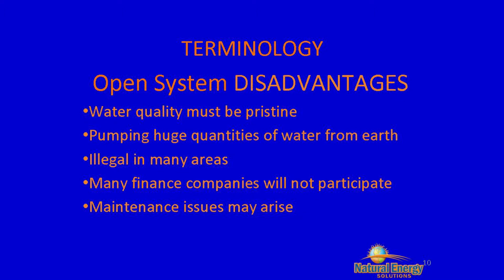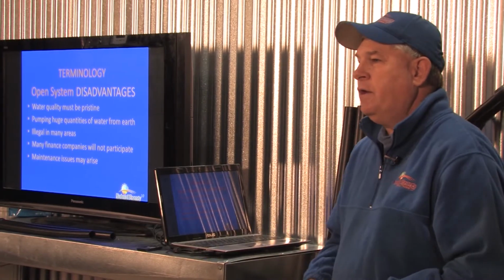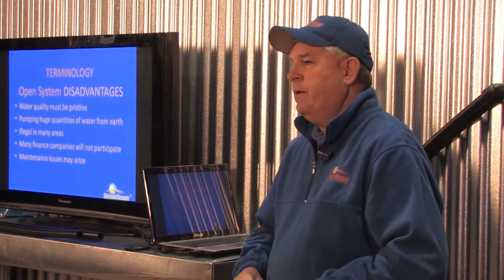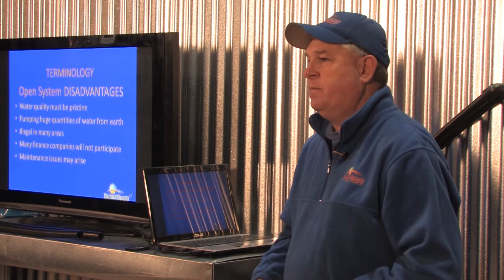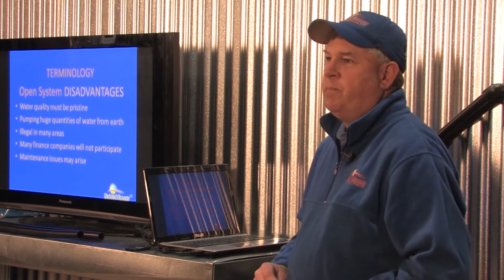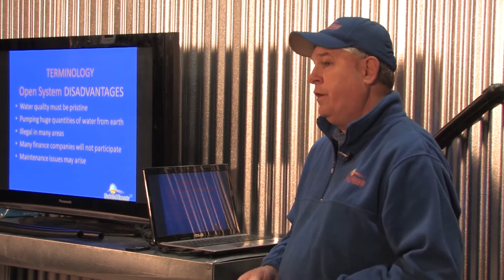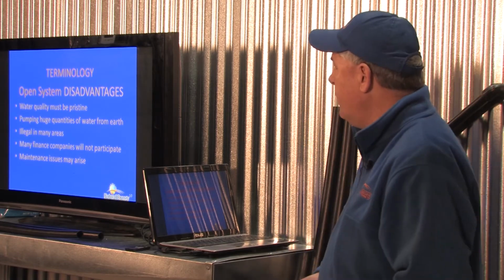Another disadvantage is the amount of water we're pumping. You're going to pump 1 to 2 gallons a minute for every 12,000 BTUs you need for your house. If you do that math quick, a typical house that needs 50 or 60,000 BTUs, that's about 3.7 million gallons of water a year you're going to pump out of the ground.